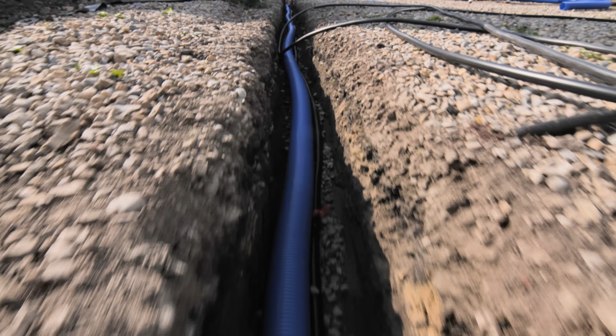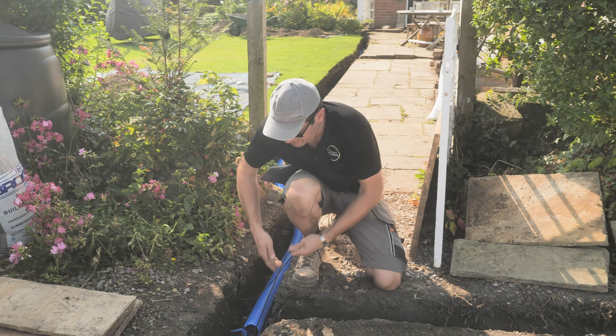Right, so we're cracking on with the install now. The customer dug us this fantastic trench, saving us a lot of back-breaking digging. Inside that trench we've put an 80mm duct containing a 16mm 3-core armoured cable. Now a lot of people will be wondering why we've installed a 16mm 3-core — that's massively oversized for a 7 kilowatt Zappi, and it is, absolutely. But if we move along here, I'll reveal why we've put a 16mm in.